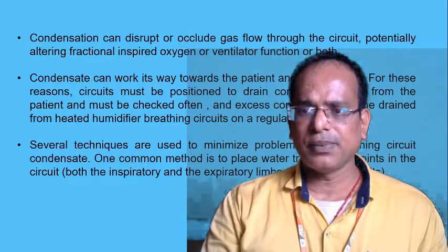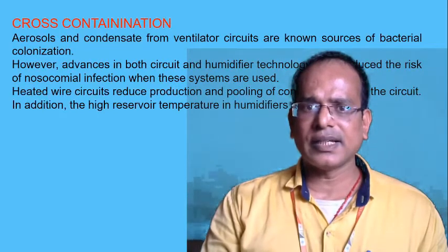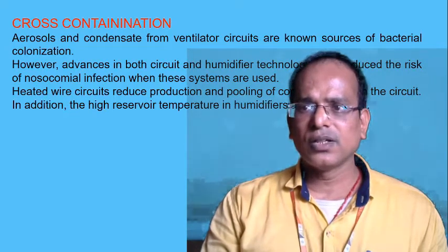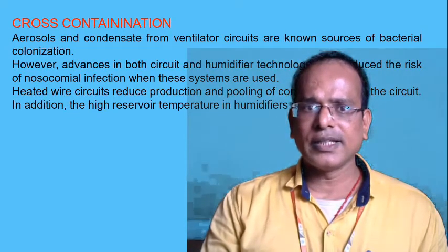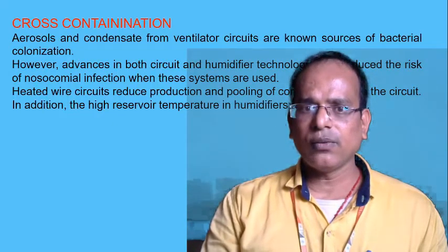Cross contamination: aerosols and condensate from the ventilator circuits are known as a source of bacterial contamination. However, advances in both circuit and humidifier technologies have reduced the risk of nosocomial infection when these systems are used. A heated wire circuit reduces the production and pooling of condensate within the circuit. In addition, the high reservoir temperature in the humidifier is bactericidal.